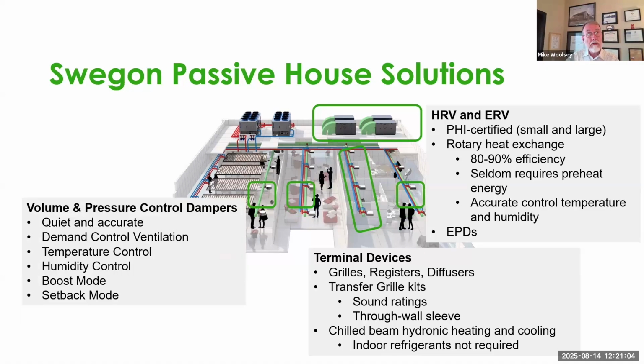We need pressure control to achieve demand controlled ventilation. So if you've got an apartment that's pretty far away from the air handling unit or the ERV, that unit doesn't get starved for air, nor does the apartment closest to the ERV get too much air. That's all accomplished with pressure control, and our dampers achieve that.